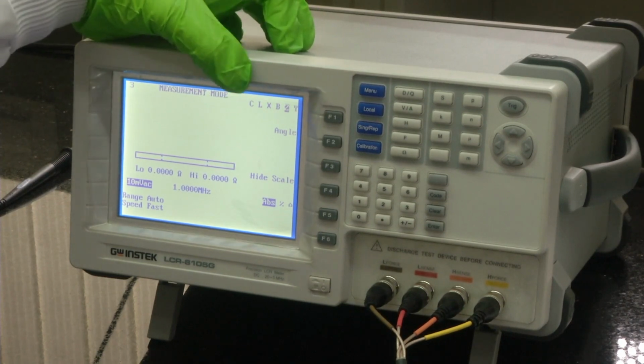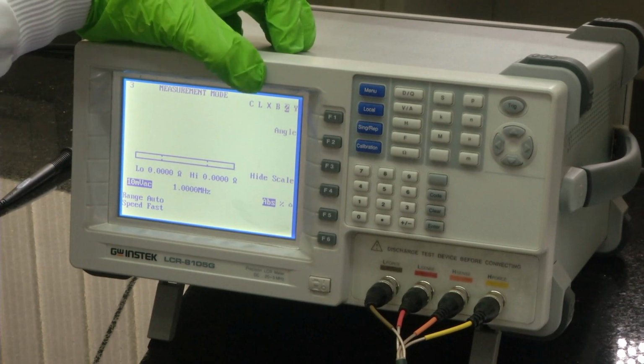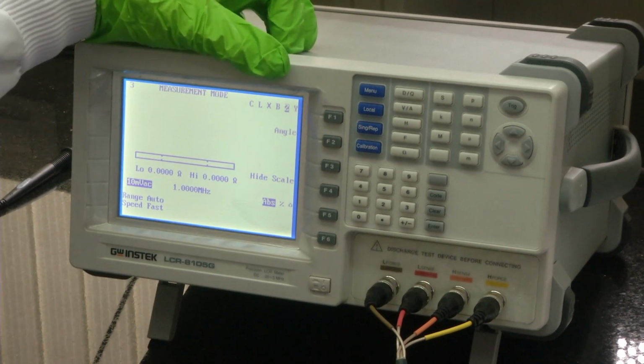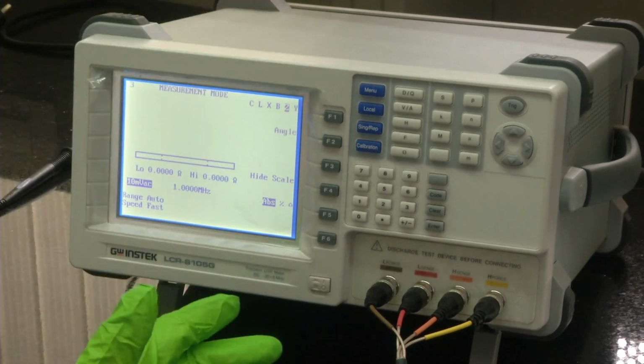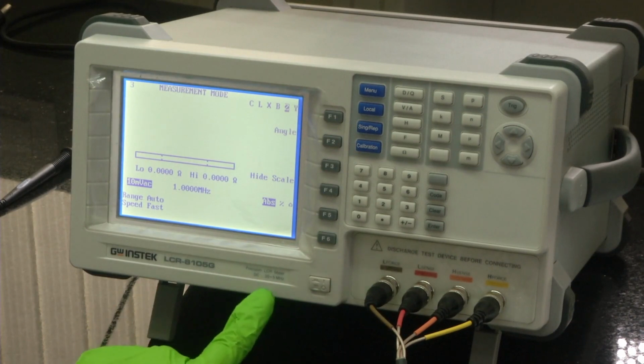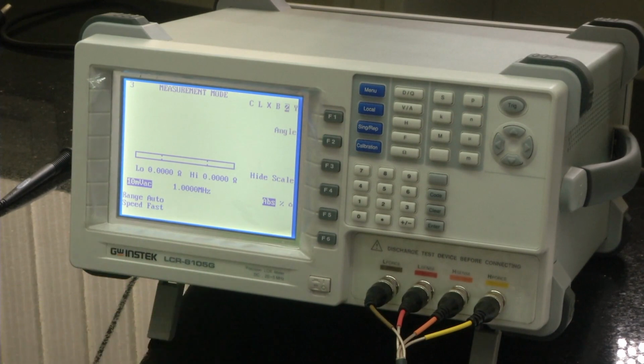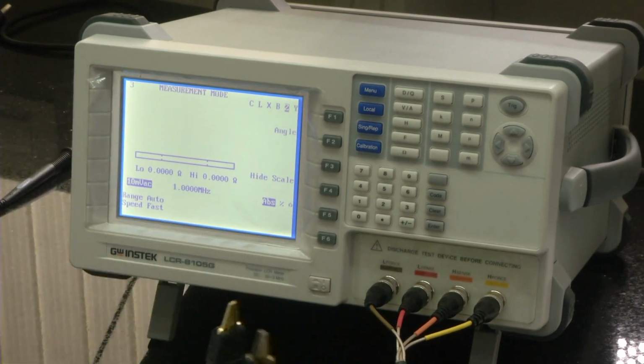Capacitance value, inductance value, reactance value, admittance value all make sense only if you do a frequency based measurement. That is why this equipment is useful. It can measure across a range of frequencies. Now these probes which we saw, they are both a source and a probe.